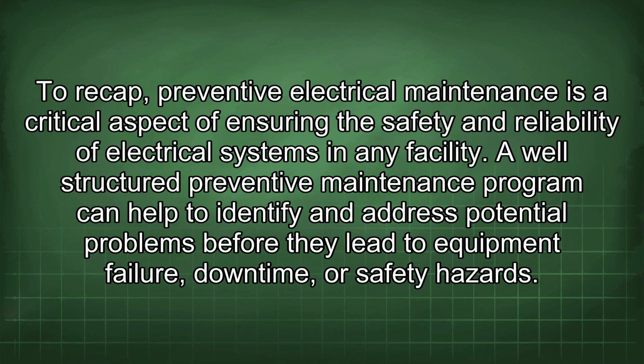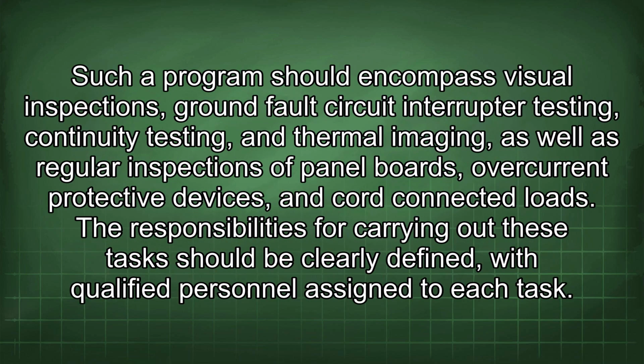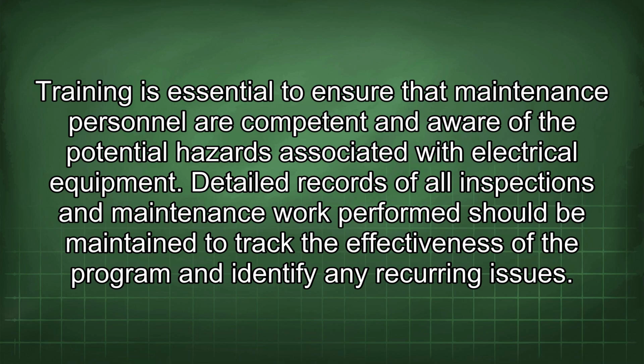To recap, preventive electrical maintenance is a critical aspect of ensuring the safety and reliability of electrical systems in any facility. A well-structured preventive maintenance program can help to identify and address potential problems before they lead to equipment failure, downtime, or safety hazards. Such a program should encompass visual inspections, ground fault circuit interrupter testing, continuity testing, and thermal imaging, as well as regular inspections of panel boards, overcurrent protective devices, and cord-connected loads. The responsibilities for carrying out these tasks should be clearly defined, with qualified personnel assigned to each task. Training is essential to ensure that maintenance personnel are competent and aware of the potential hazards associated with electrical equipment. Detailed records of all inspections and maintenance work performed should be maintained to track the effectiveness of the program and identify any recurring issues.